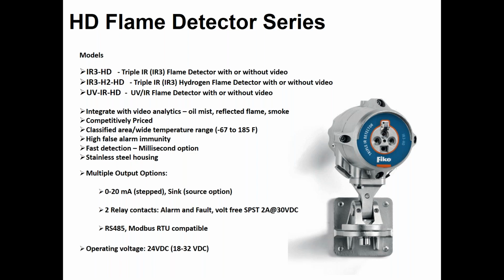Oil mist could potentially be detected prior to an explosion or flame where the detector is not used, and you're detecting before the fire occurs. Competitively priced, the temperature range, -67 to 185 degrees F. Very high false alarm immunity. The system can be used for millisecond or high-speed operation connected to a high-speed deluge system. Class 1 Div 2 housing and stainless steel, so it can be used in areas where you have chemicals. 0 to 20 output, alarm and trouble outputs. This is all on board the detector itself.